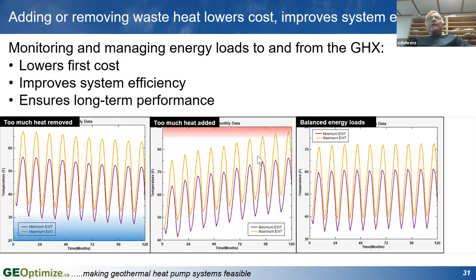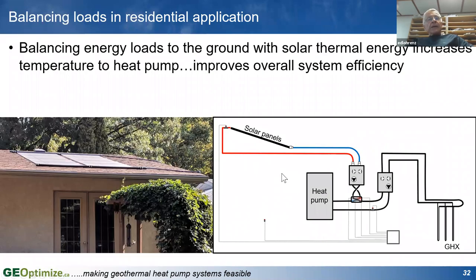So we're basically trying to balance the loads that we're trying to shove in and out of the ground. In my own house, for example, what I've done, because you're all aware of how cold it gets in our climate in the winter, minus 40, we do maybe 200, 250 hours of air conditioning on a typical year. My house runs about 2,500 hours, about 10 times as much for heating. So I'm extracting a whole lot more heat from the ground than I can put back into it. So what I've done in the last year is add a small solar panel to the roof, dump it into the ground heat exchanger, and try and balance those loads.